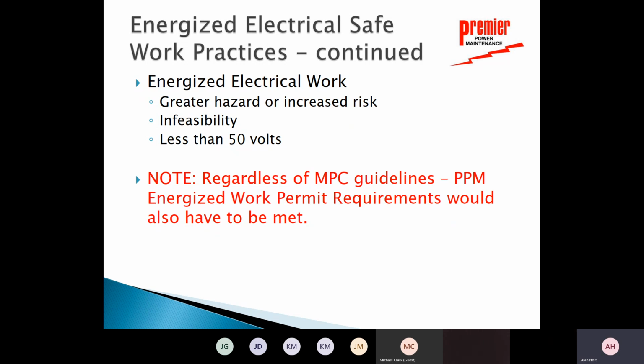Now, energized work, less than 50 volts. Less than 50 volts, there are no regulations, so you can work on equipment that operates at less than 50 volts. That would not require an energized work permit.